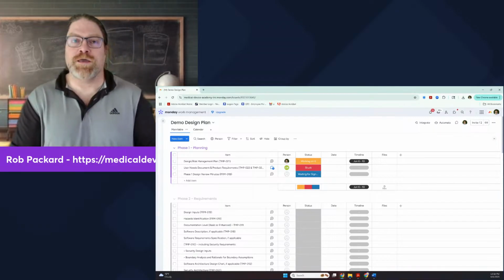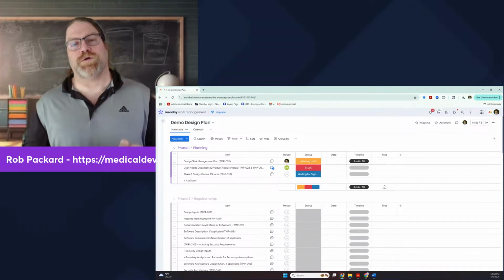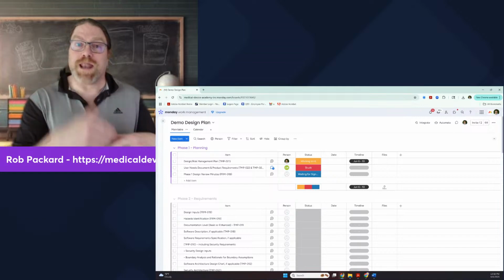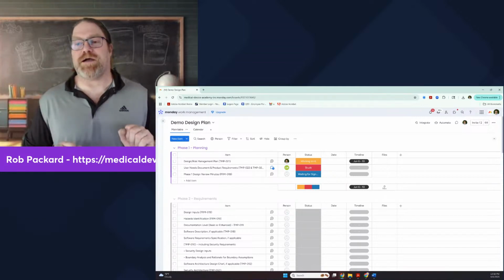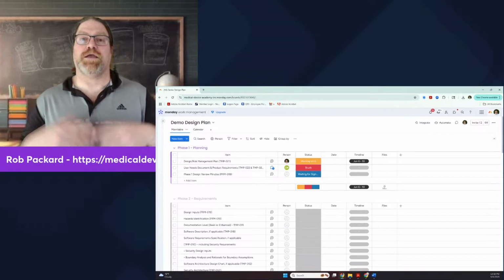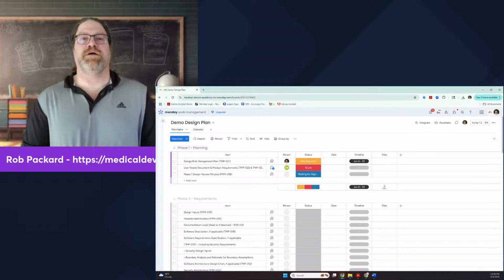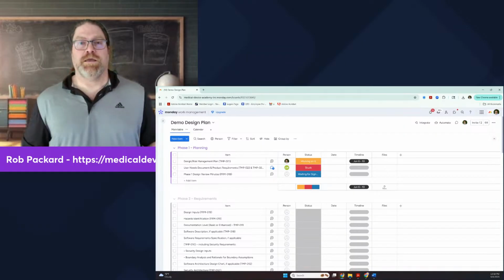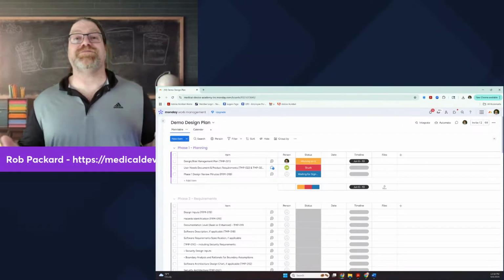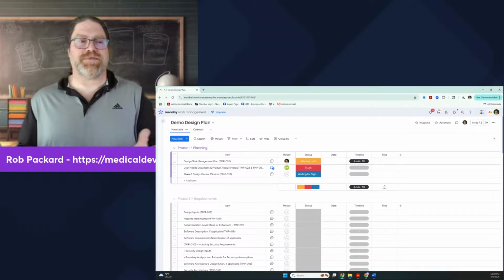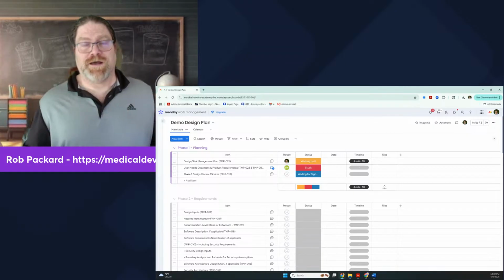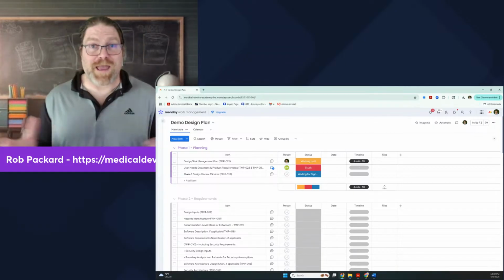And number 2, you're not ready yet is also a lame excuse because I told you, you can update. You're supposed to update it as it progresses. I want a draft. It's just a draft. So when somebody comes and asks you, have you started your design history file? Yes, I have. I've started my design plan. Yes, I have. We're good. But other people tell me, no, we haven't. We don't even have a design procedure yet. Well, where are you? Well, ready to submit to the FDA. Huh? How can you be ready to submit to the FDA and you haven't got a plan yet? That doesn't compute, but it happens all the time.